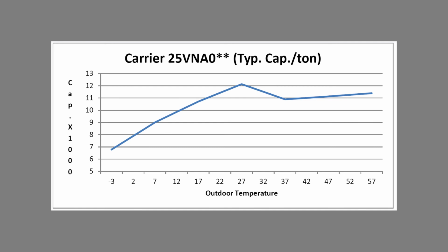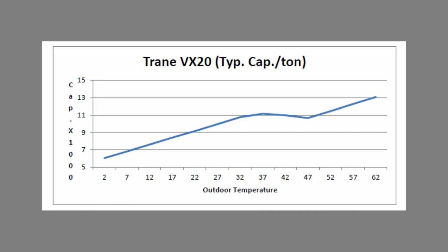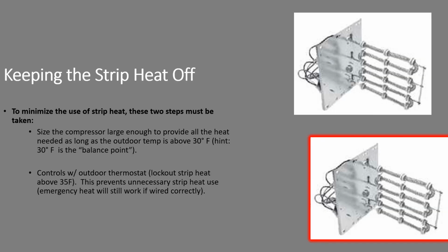Does this make sense? Yes, we don't need full capacity from the compressor at 52 degrees. It's much more likely that we'll need the full capacity at 27 degrees. And we can see that it dives off the colder it gets. Here's another system that's an extended capacity system. It's a little flatter. This one does have higher capacity at warmer temperatures, but notice this very flat spot here, roughly between 27 and 47. That's sort of where we live in the Northwest, so your capacity remains flat through that temperature range.